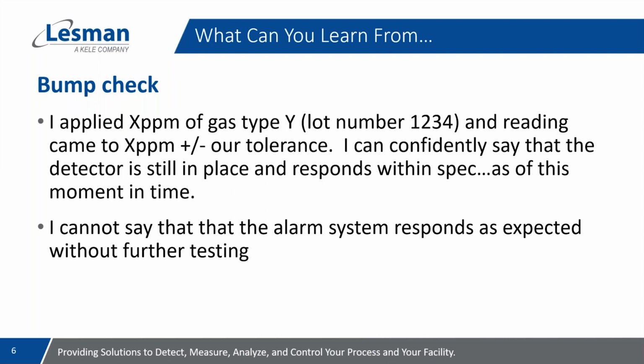Most newer design transmitters allow you to bump test a sensor without setting off alarms by going into some sort of maintenance mode, holding the outputs to the control system. But I'm not aware of any that have a timer function to reach the target level during a bump check. And of course, unless you force the output, you also don't know if the alarm functions are still operational. You can say that the sensor responds to the target gas within your acceptable tolerance, but you can't say anything about the rest of your system.